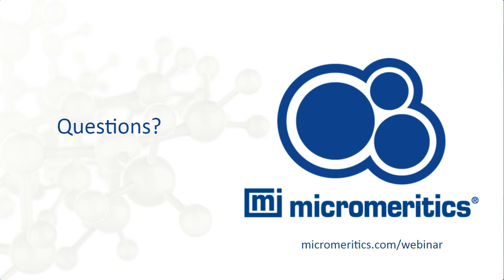We've got a question now relating to crystalline materials rather than carbons. Do you have recommendations for both probe molecule and the fluid, and the temperature for the fluid for zeolites, and then also for something like a metal organic framework, a MOF? Well, the recommendation is kind of natural, to use argon. Avoid nitrogen, because nitrogen has these interactions with polar groups, which are a lot of them in zeolites.